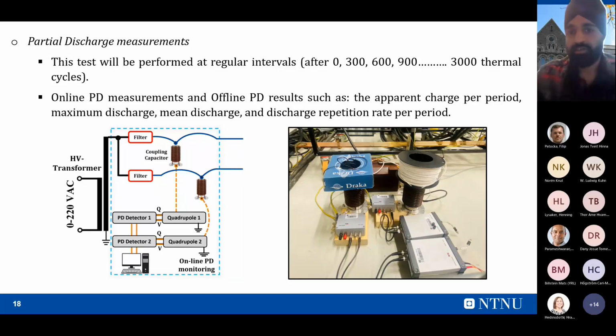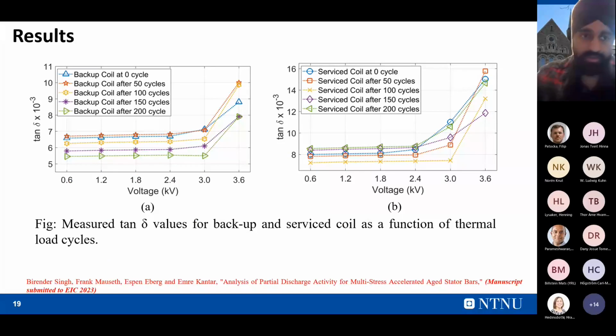So this is the partial discharge setup. This is coupling capacitor 1 and coupling capacitor 2. Now the results obtained from the tan delta are shown here. This side is the backup coil, the coil which is not in use, but they are manufactured at the same time, and this is the service coil. So now I have connected 0 cycle, 50 cycle, and after every 50 cycles we have conducted the tan delta measurement and partial discharge measurements.